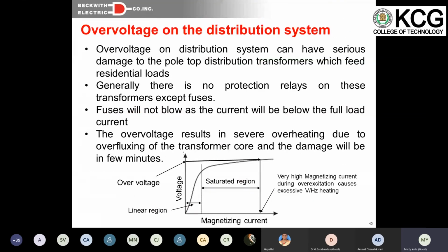Also, the local distribution transformers, which bring the voltage down from 11 kV to 230 volts, are affected. With a high voltage, if you look at the magnetizing BH characteristic of a transformer, you get a large magnetizing current. Typically it is less than 1%. At those high voltages, you hit like 60 to 70%. That is still less than the full load current, so the fuses won't blow, but the transformer gets heavy overfluxing, which heats up the core, and after a few minutes they start popping. That means they will get destroyed. You'll see fires start coming up from the poles.